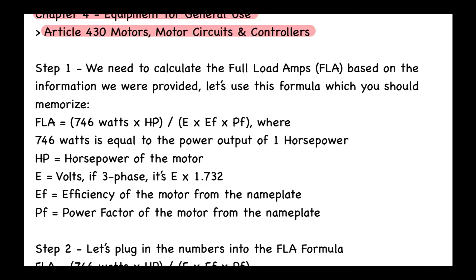Step number one: we need to calculate the full load amps, the FLA, based on the information we were provided. Let's use this formula which you should memorize. FLA is equal to 746 watts times the horsepower of that motor, then we divide that by the voltage times the efficiency times the power factor, where 746 watts is equal to the power output of one horsepower.